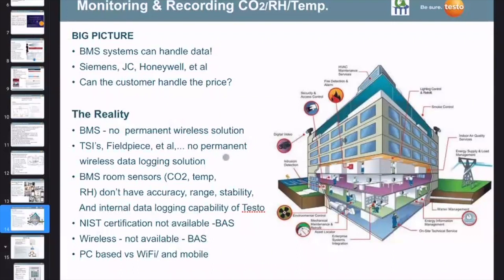But the difference is that the sensors that are provided by the building contractors are designed to measure and send an output to do something, either to open up a reheat valve, or to open up or close a VAV box, or to effectively change the speed of a variable speed fan motor, to change the supply air volume or exhaust air volume. These are measure and control sensors. They are not measure and data log sensors. So as a result of that, it's a really different beast.